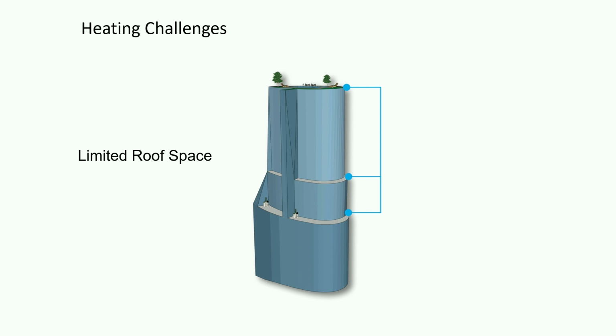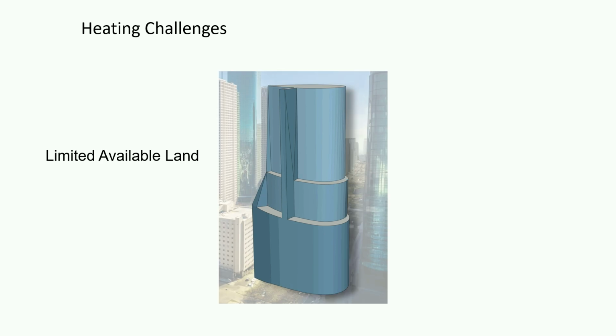Well, we've got to use geothermal. We've got to use some other technologies to open up that roof space. But we're going to be limited. Because of the footprint and, again, the building size, you have to understand that and see what you really have for available space, okay? And then, again, available land. These are generally on postage stamps, and if you have a 50, 60-story building, that's a lot of square footage to heat and cool with a very limited ground area.